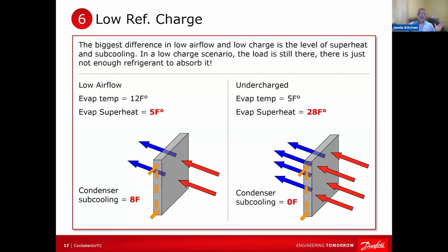All right. Your subcooling will also change a little bit. It can go down as your load drops because guess what, people? Do you know what determines the amount of subcooling you have? It's one thing, and that is the temperature difference between the refrigerant and whatever it is you're dumping heat into. So guess what? A bigger condenser doesn't give you more subcooling. It gives you less because it allows your approach temperature between the air and the refrigerant to get smaller. That means you're going to save a boatload of energy because your compression ratio is going to be smaller, but your subcooling is going to be less.